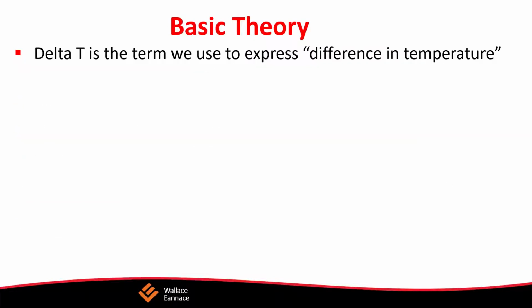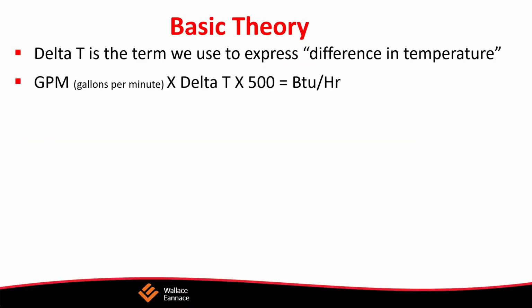Now, what is the delta T? The delta T is a term that we use to express the difference in temperature. That's very simple. In typical hydronic systems, we have a 20-degree delta T. More modern systems, we maybe get a 30, 35, or 40 degrees delta T. In some systems, you may have a very small difference of temperature.